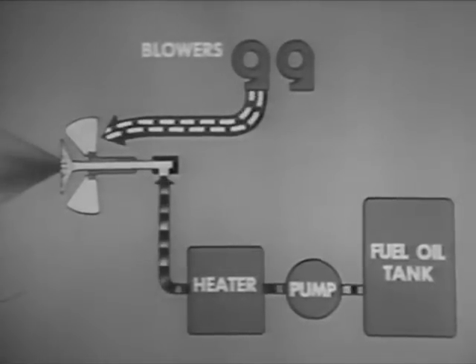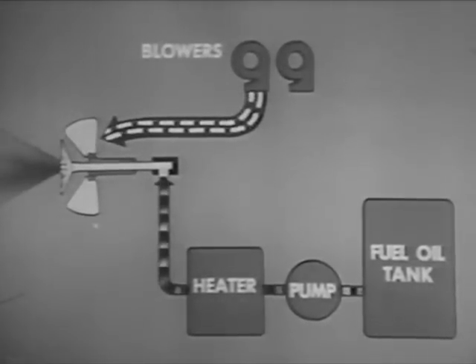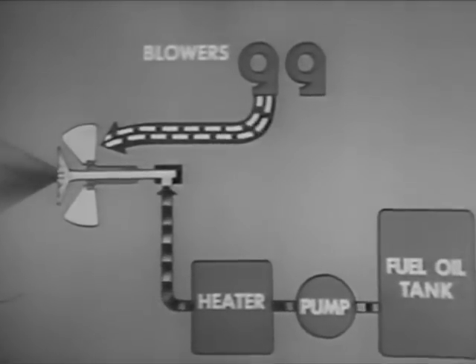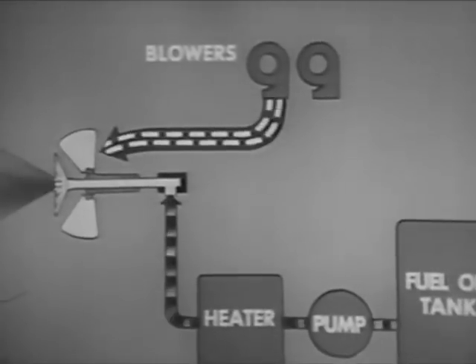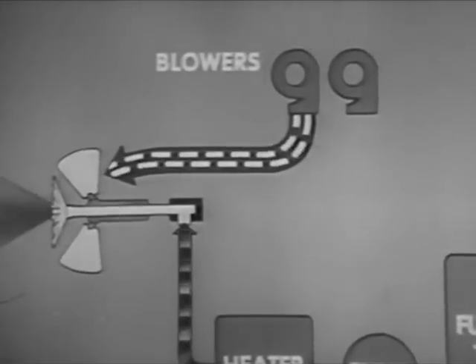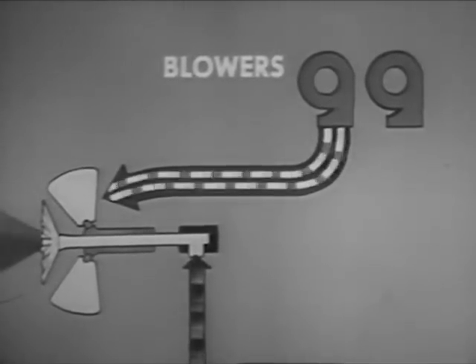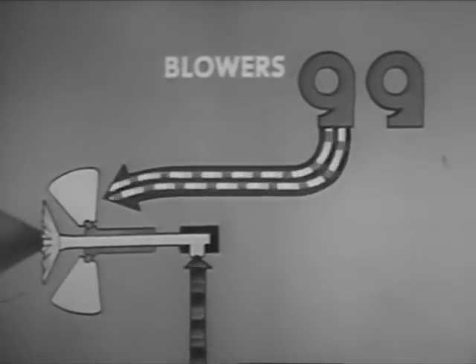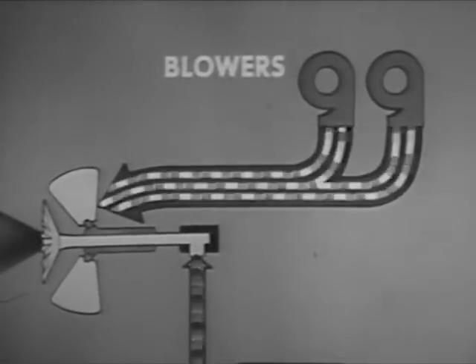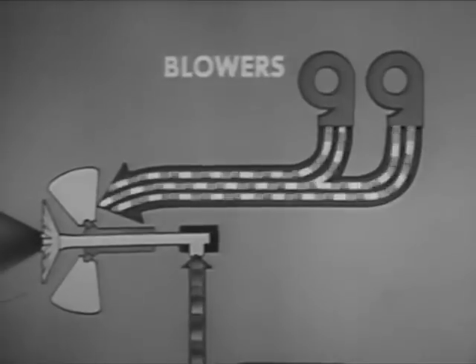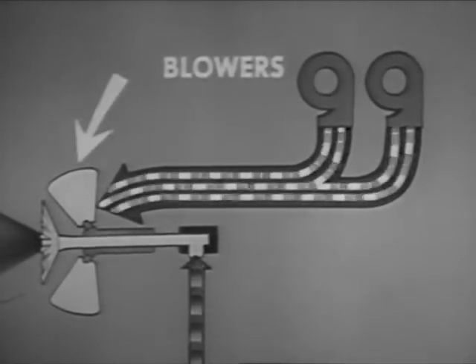Controlling the forced draft blowers is the principal method of controlling the quantity of air reaching the burner. For example, to increase the air a moderate amount, you increase the speed of the blower in service, or if even more air is needed, you cut in another blower. You can make minor adjustments in the air supply with the air doors.